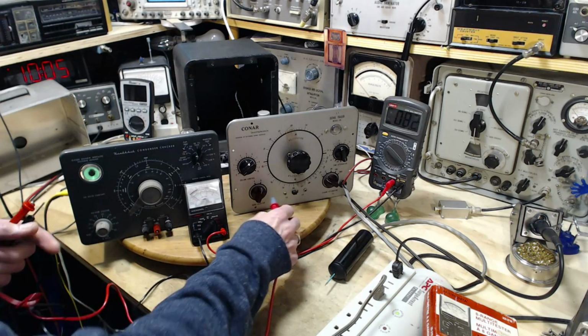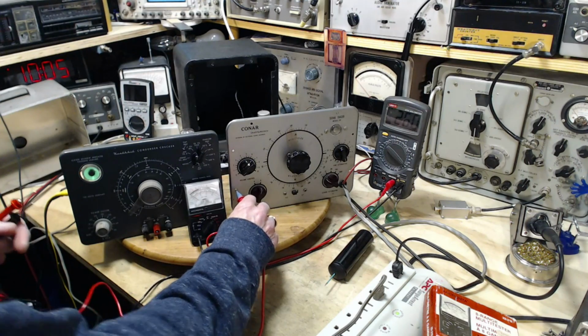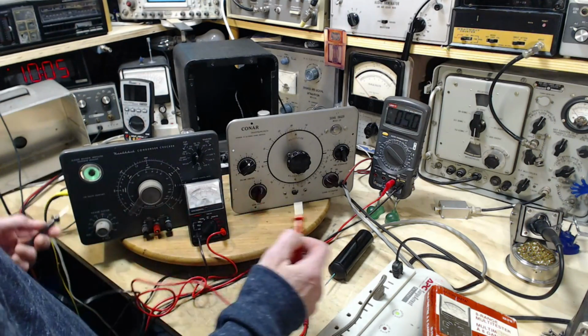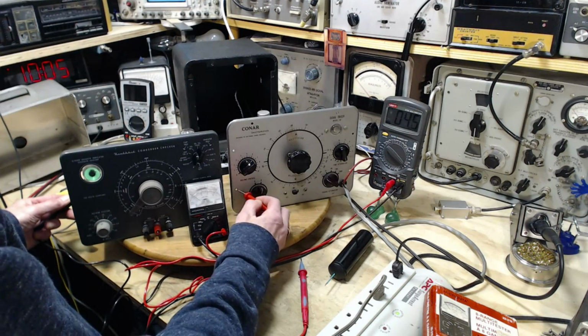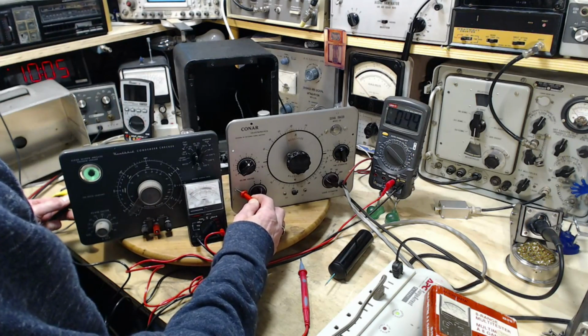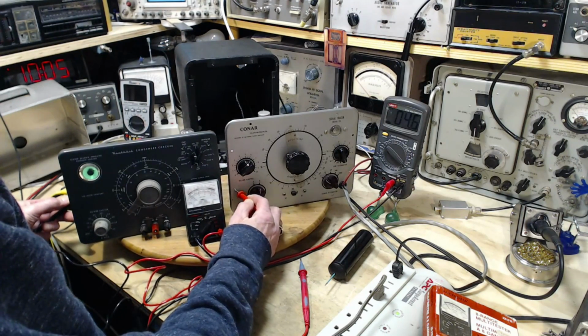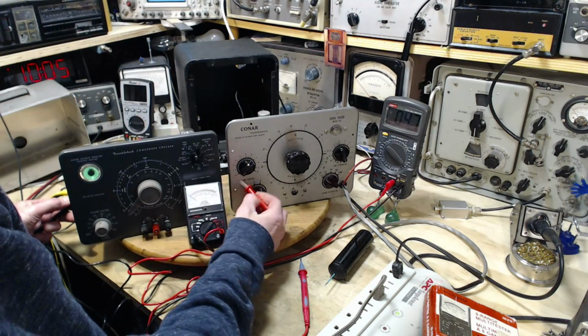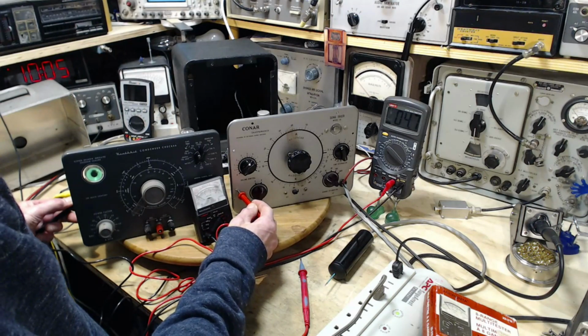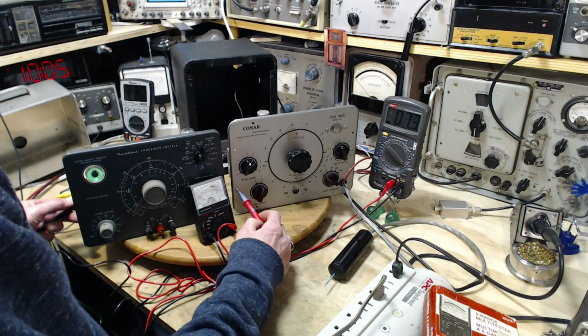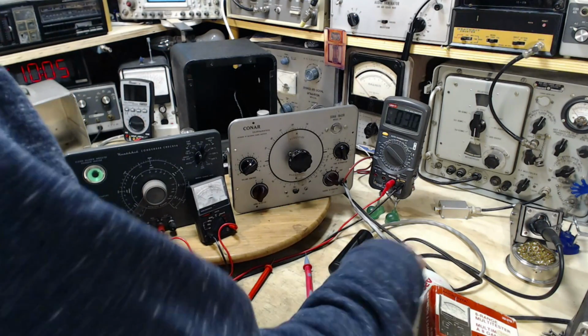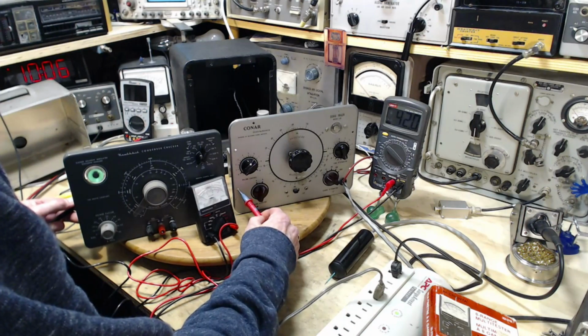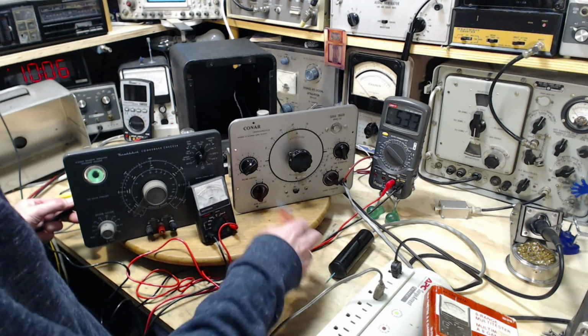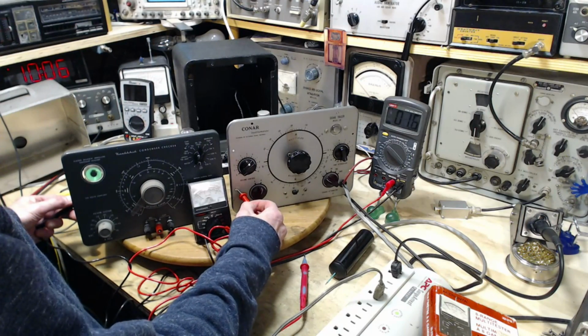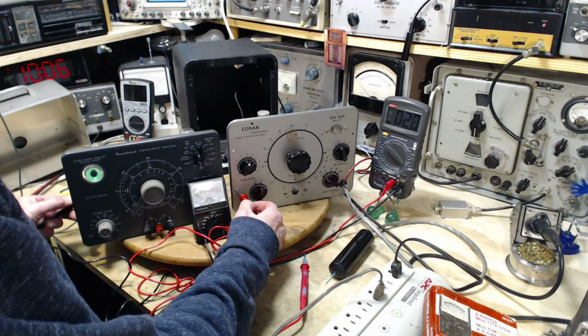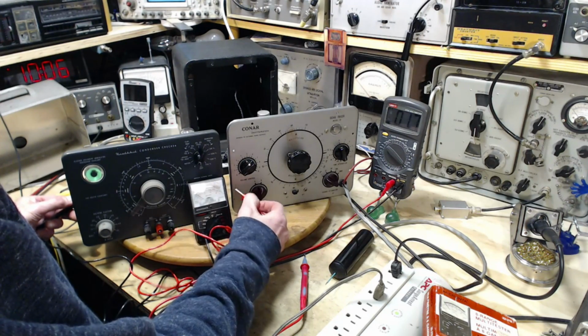Oh, let's read with the real one. I shouldn't say real one, the digital one. So we're looking at 26 volts. Can we see 26 volts on this guy? So you probably can't see it, but the meter is lifting up about the width of a needle. Going around. Now we're measuring 50 volts AC with the high impedance meter. With the low impedance meter we measure. So you know there's something there, but it's barely moving the needle.